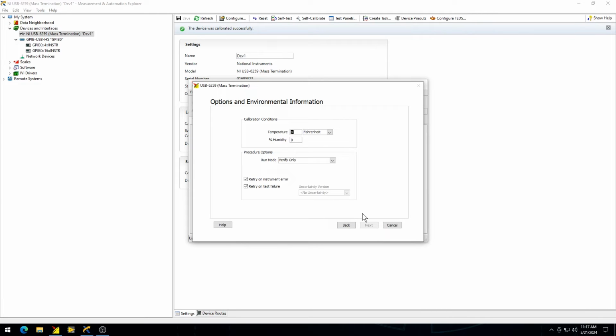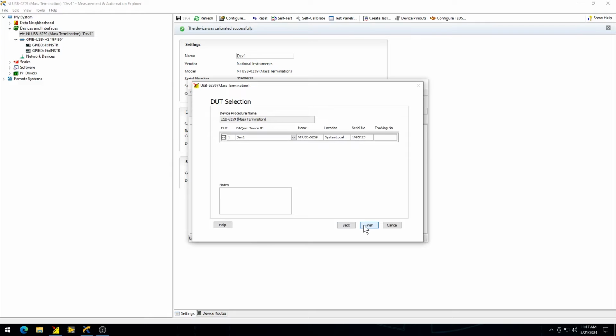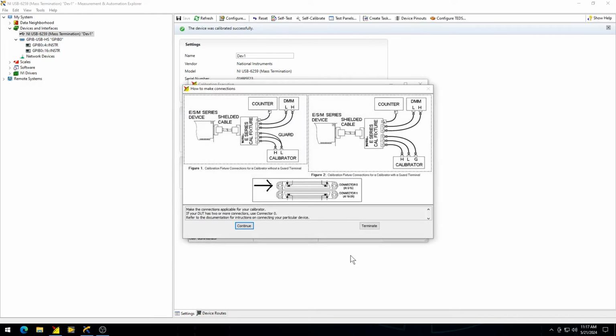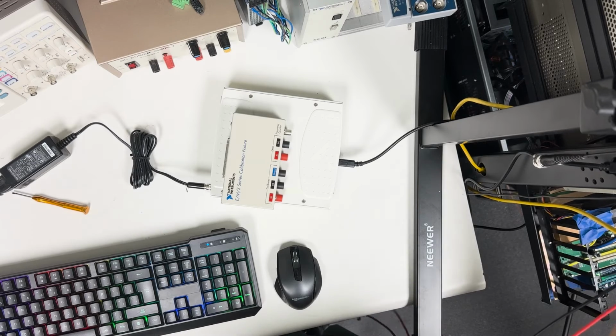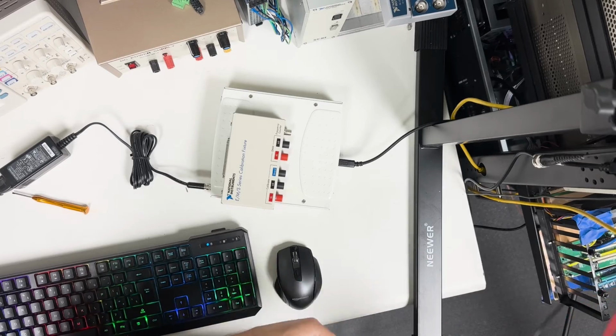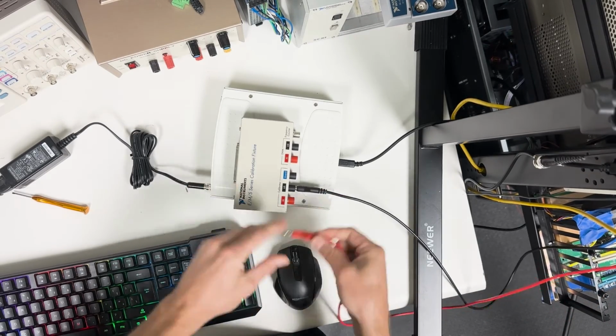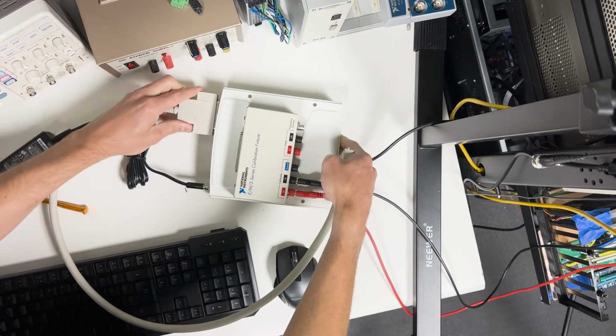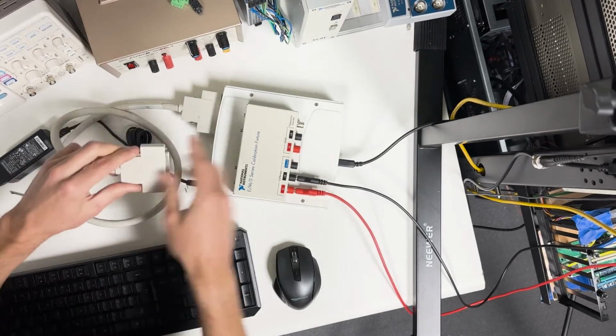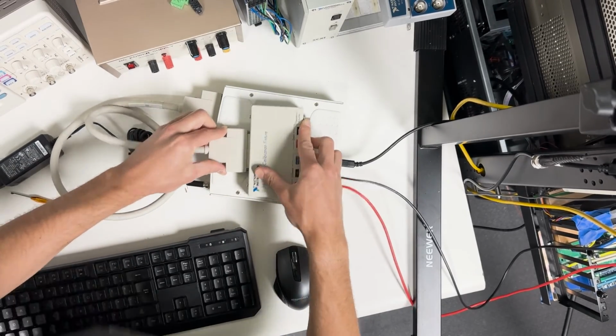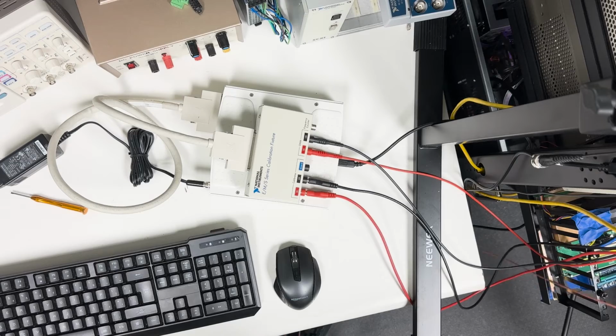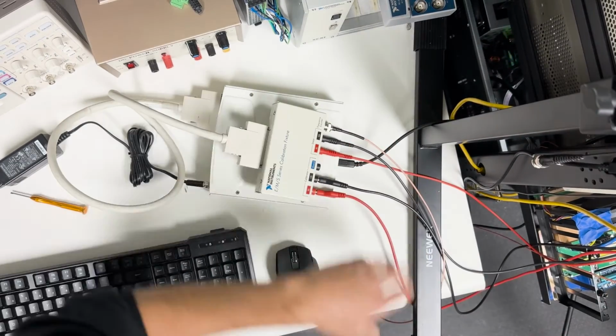Prepare for calibration. Record the temperature and humidity percentage as prompted by the application. Gather the necessary equipment: an E-Series calibration fixture, banana plug cables, a BNC cable, and a shielded cable. Connect the banana plug cables to both the calibration fixture and the calibrator. Connect the shielded cable to the back of the calibration fixture and the USB-6259. Connect the BNC cable to the calibration fixture and a counter.